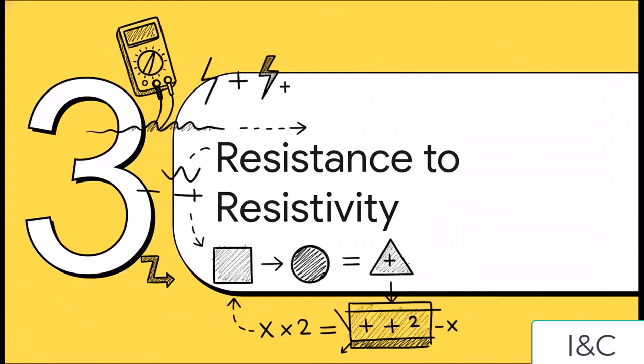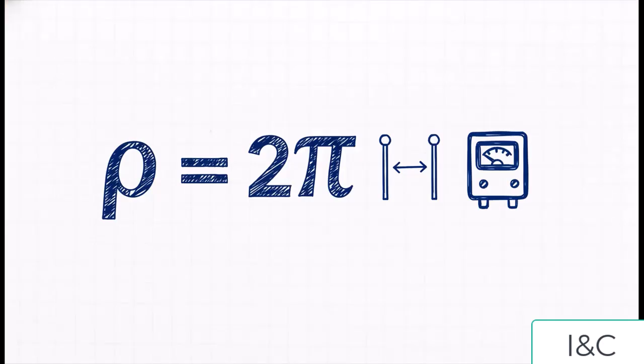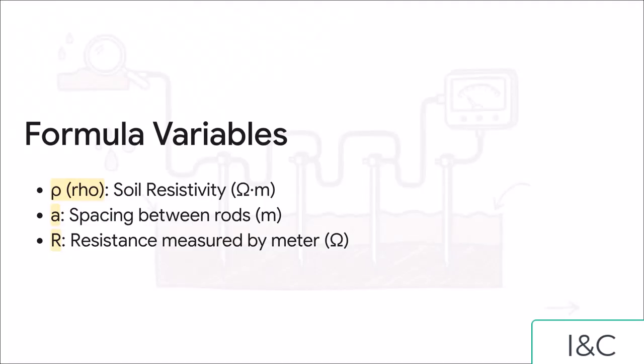So how do we get from that resistance number on the meter screen to the soil resistivity value that we actually need for our designs? Well, the answer is a pretty simple formula. This right here is the Wenner formula, and trust me, it's simpler than it looks. All it's saying is that resistivity, the Greek letter rho, is just 2 times pi times A times R. Let's break that down real quick: R is easy, that's the resistance value we just got from our meter in ohms.